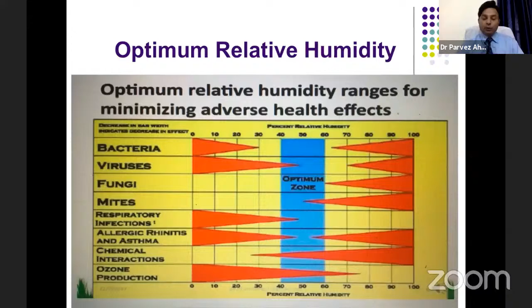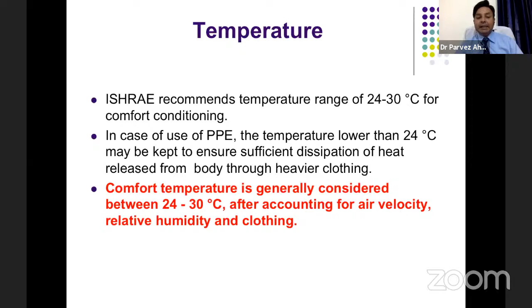Temperature is directly related to the comfort level of healthcare providers as well as patients. ISHRAE recommends a temperature range of 24 to 30 degrees Celsius for comfort conditioning. In case of personal protective equipment use, such as in ICUs or operation theaters related to coronavirus, a temperature lower than 24 degrees Celsius may be kept to ensure sufficient dissipation of heat released from the body through heavier clothing. Comfort temperature is generally considered between 24 to 30 degrees Celsius after accounting for air velocity, relative humidity, and clothing.